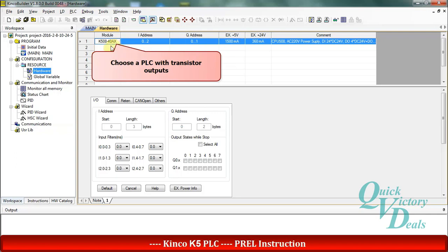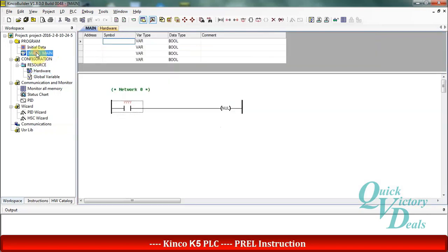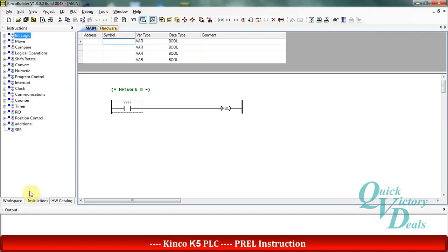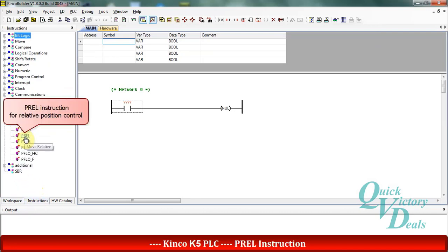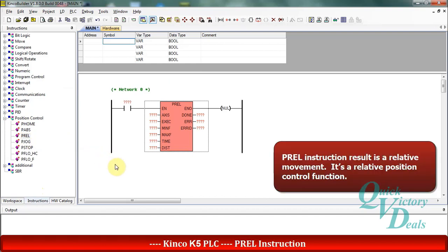Then we can come back to our main program environment. We should go to the instructions part and in the position control category we can find P-REL function. It is a relative position control function, and it will cause some movement from the current position until the target distance that we set in the distance operand.